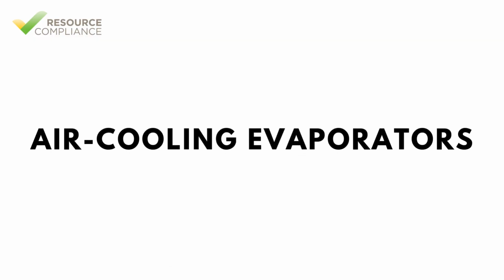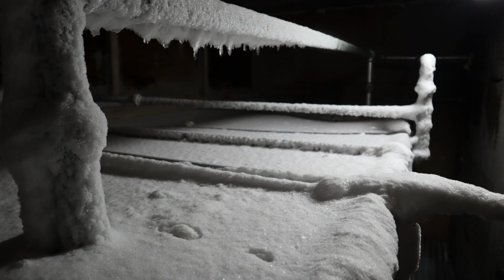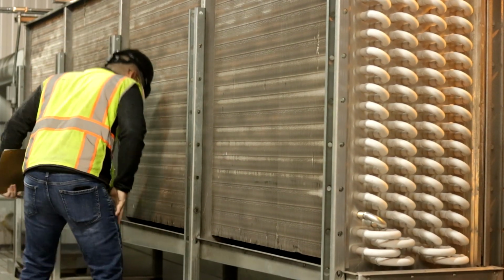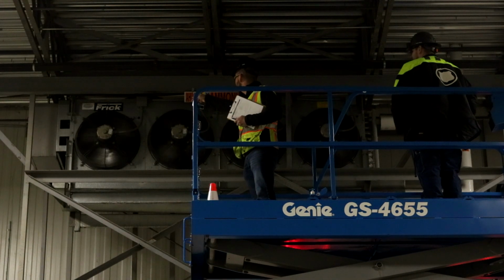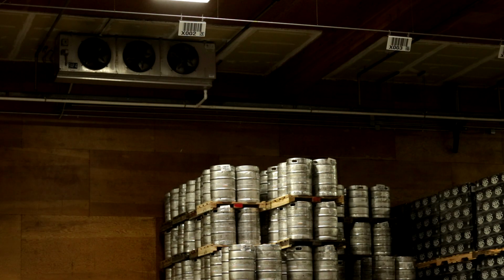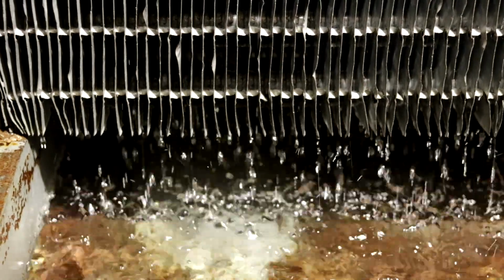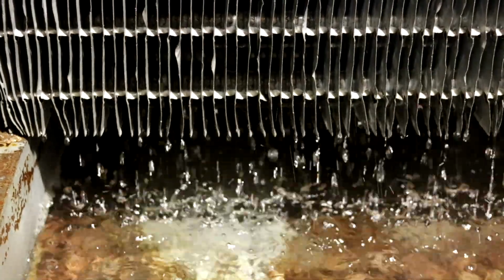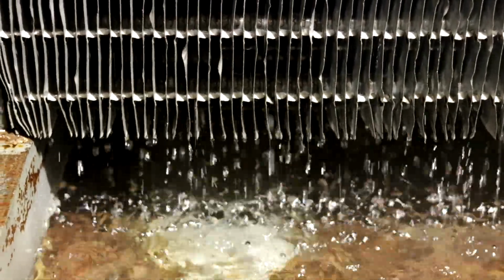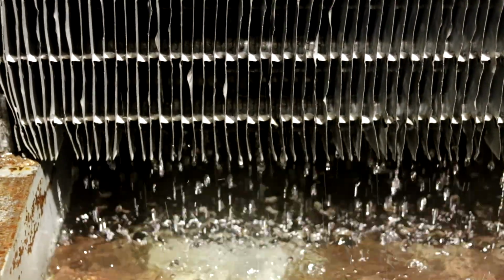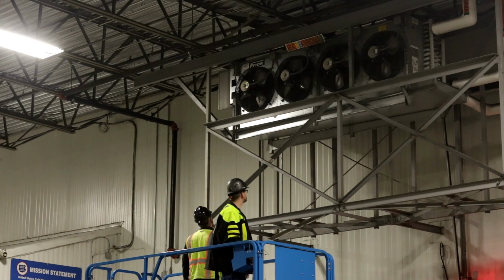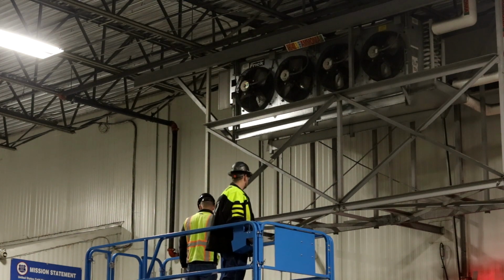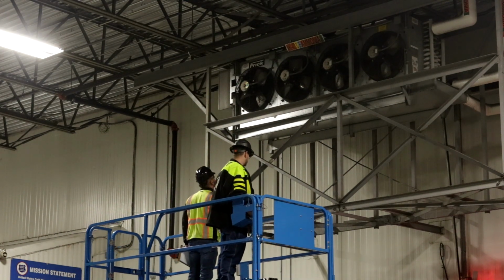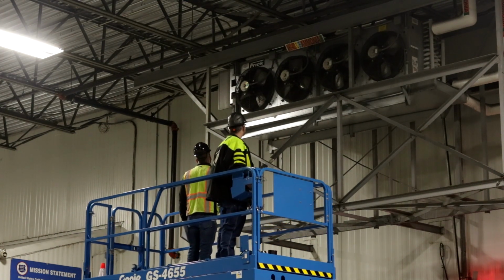Air cooling evaporators should be inspected weekly for abnormal sounds and vibration. At least monthly, the evaporator should be inspected for excessive ice buildup. Every 6 months, a thorough inspection should check for damage to external parts, fan blade cracks, dirt buildup, adequate protection from traffic, and obstructions in the drain pan. Air cooling evaporators do not have many testing requirements. However, it is recommended that a defrost cycle be observed every 3 years. Maintenance on air cooling evaporators is straightforward. The tubes and fins should be cleaned at least annually, and fan motor bearings lubricated as recommended by the manufacturer.